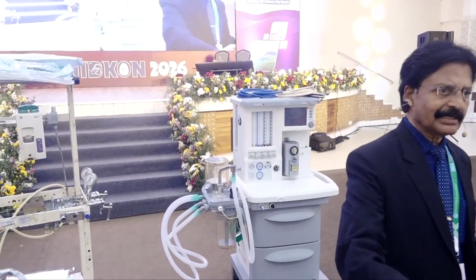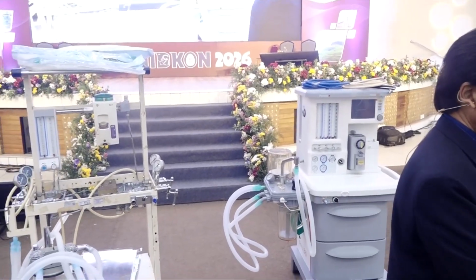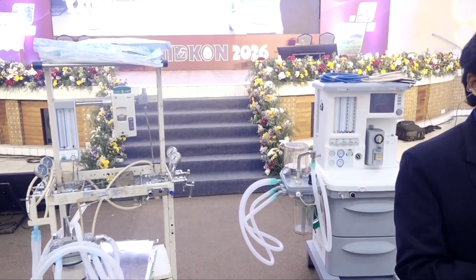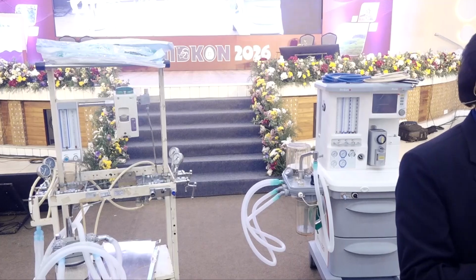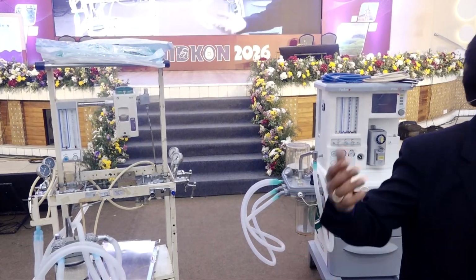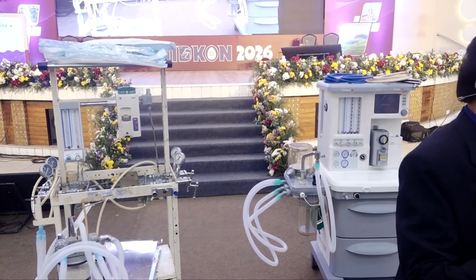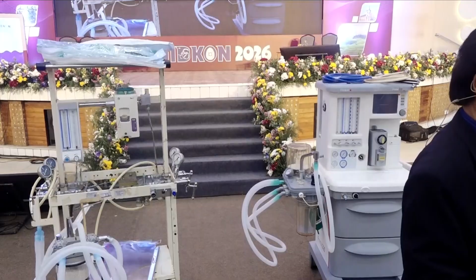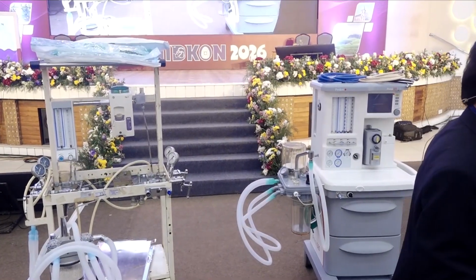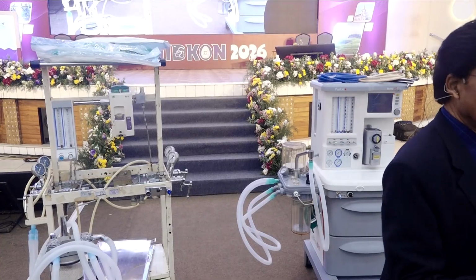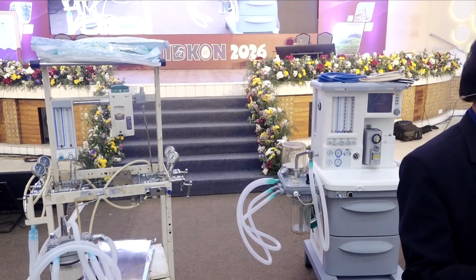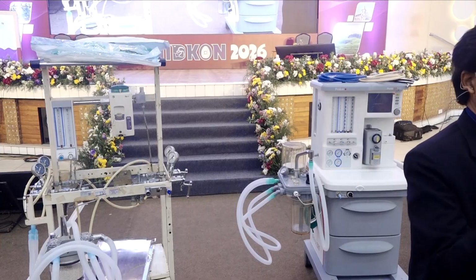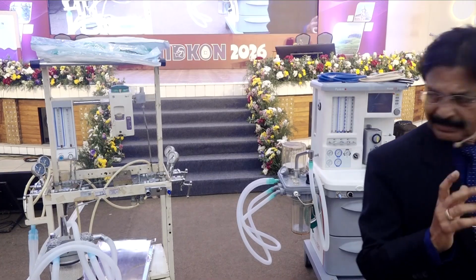So instead of concentrating on the patient, you will have to concentrate only on your flow meters, and keep on adjusting. Suppose I have a pressure regulator, constant pressure gases will be flowing to the flow meters with only 45 psig, or the pipeline 55 psig, so the flow will not alter. So that is the main reason why a pressure regulator has to be there.